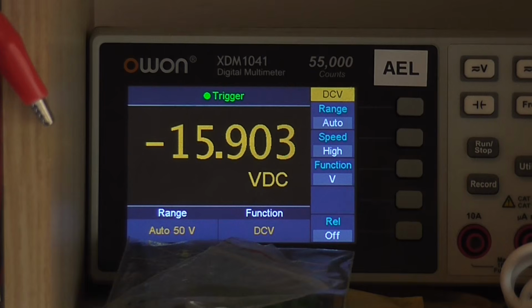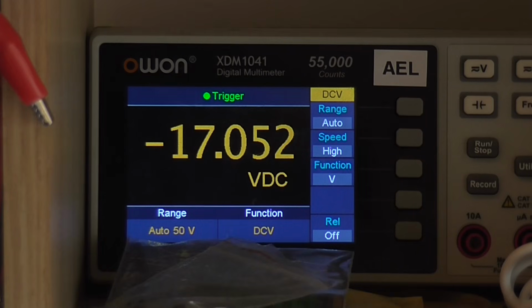I can even at this point bypass the dim bulb and we should see that voltage come back up, which comes closer to our calculated voltage. So the dim bulb was limiting the current going into the transformer, which was limiting the voltage at the secondary, which was also limiting our output voltage.